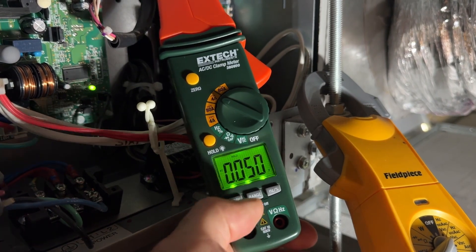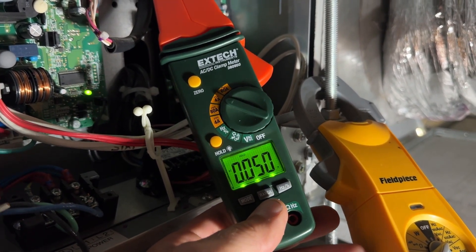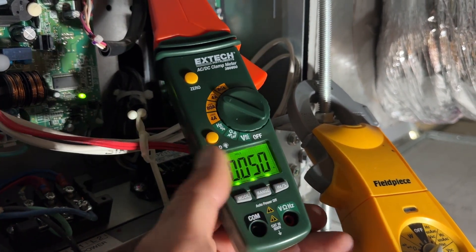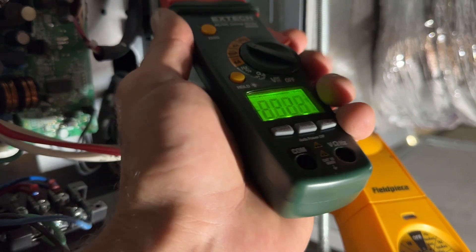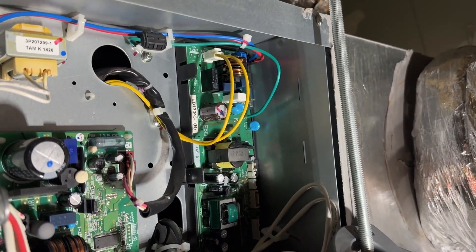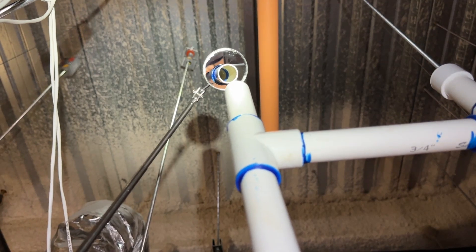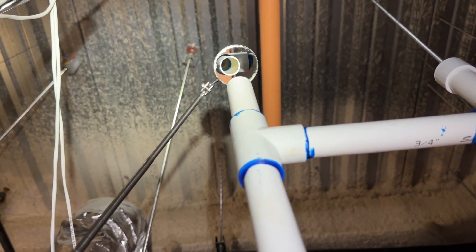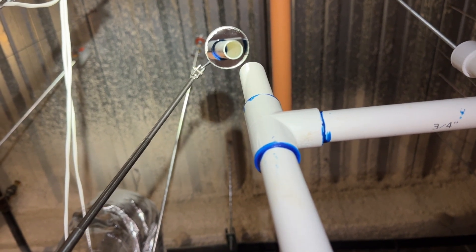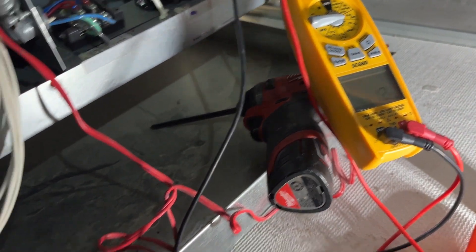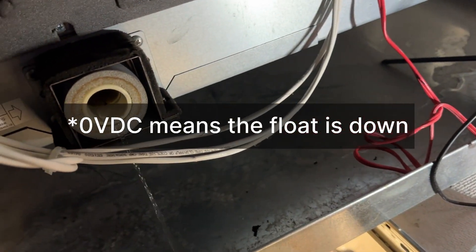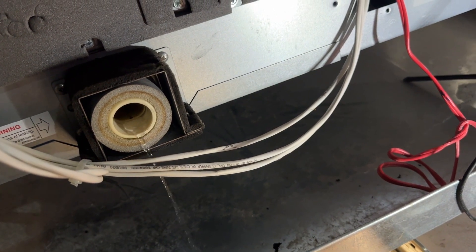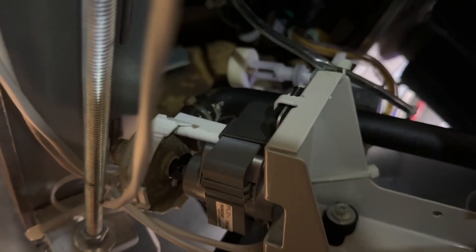It's still running with the system off. Might need to be in heat to finally shut that pump down and it's really hard to keep track of what all these different systems do under different circumstances. To simulate the pump going off I'm just gonna unplug it. It's hard to tell on the camera but I can see that the water has drained back into the pan. I'm draining it now and I want to see if this switch goes back on its own. It's normal for some water to come out of these ports no matter what but I'm sure we have a lot built up.